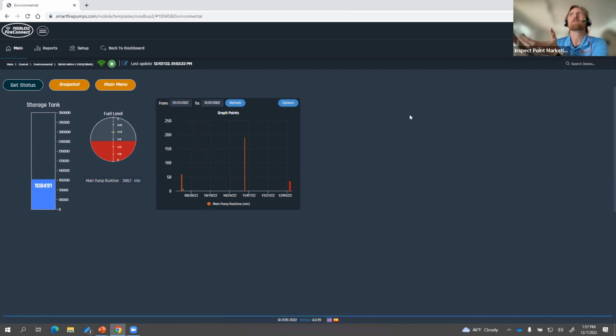I could see that the majority of fire pumps that are installed, they want a third party to come in and deal with it. So who owns that piece? It just depends who sells that piece, or who buys that piece. If the sprinkler contractor buys it and is installing it on behalf of an end user, it just depends. Does the end user want to take ownership of that piece of equipment because it's now in the building? That is up to the contractor and the end user at the end of the day. If the contractor says, I've got this monitoring option and I'm going to use it as part of our service agreement, I'll put it into your building but I will own it, then I think it's pretty straightforward that the sprinkler contractor would own it.